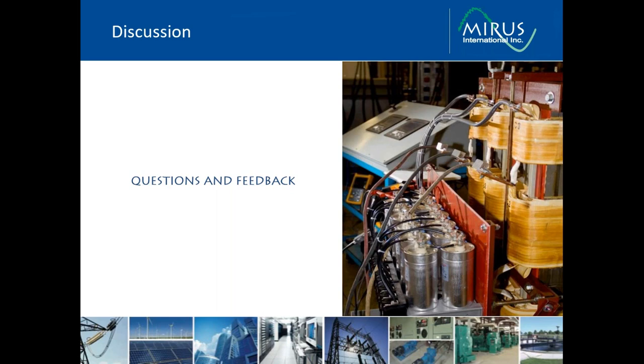I guess this one relates back to the one recently about our extreme duty model. If a filter is oversized for the load, is its performance affected? Yes, all forms of harmonic mitigation are affected by loading levels if they're lightly loaded, other than, I guess, an active filter, a parallel active filter. Parallel active filters perform even under lighter loads. But most other forms of harmonic mitigation are going to have higher current distortion at lighter loads.